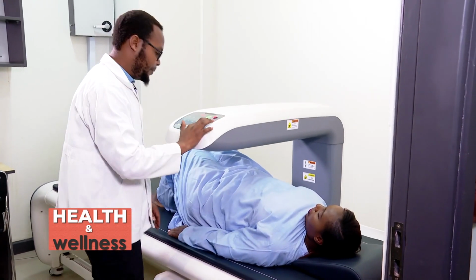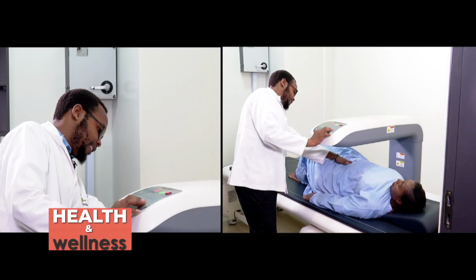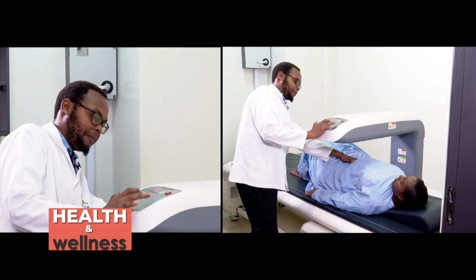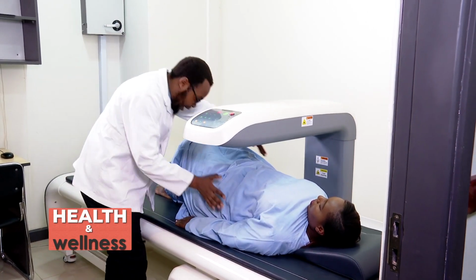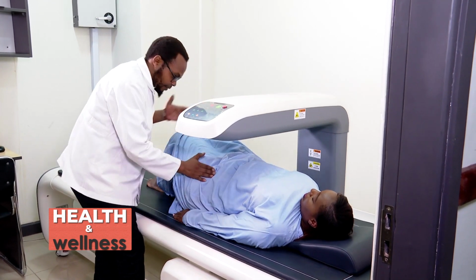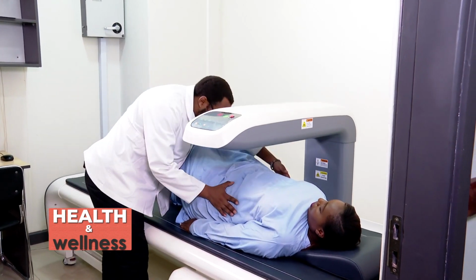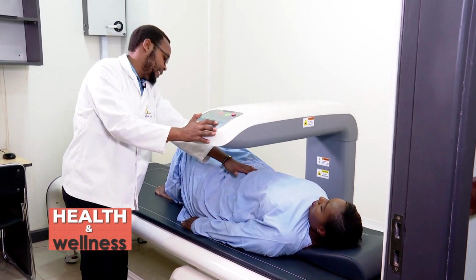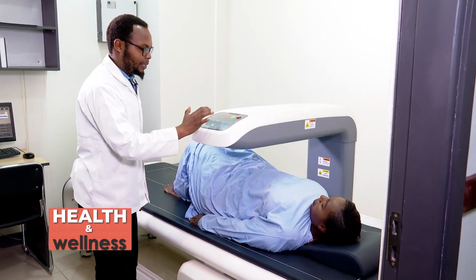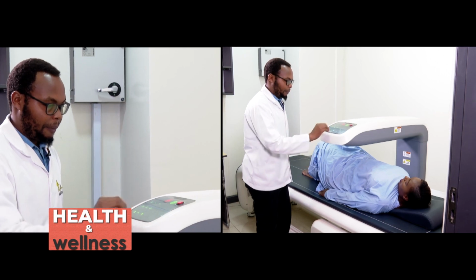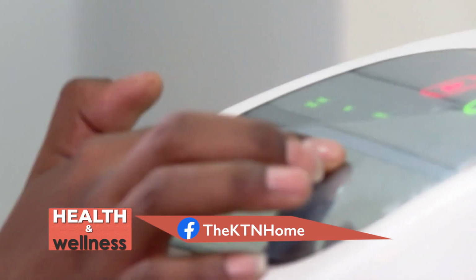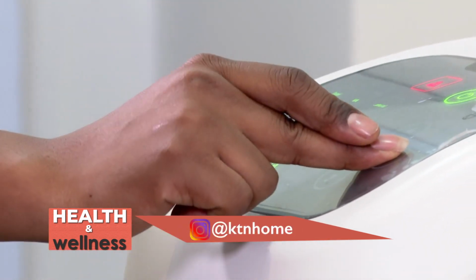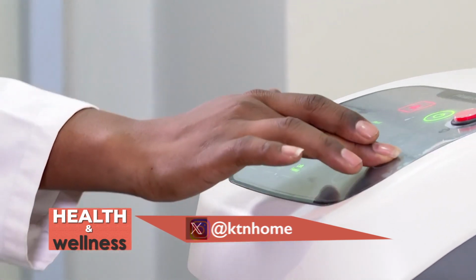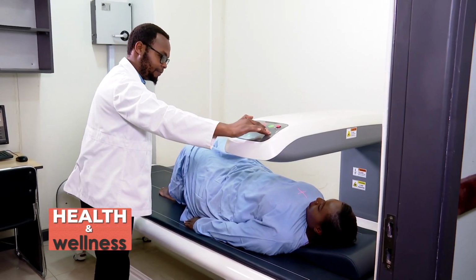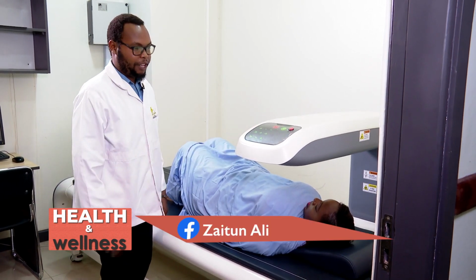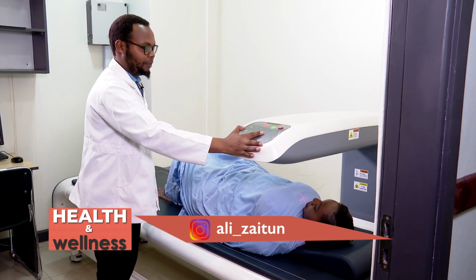So here we position the patient. The arm still moves. Patient will still remain in the same position. Make sure that the patient is well aligned at the center. We don't want to miss anything. We want to capture everything. Okay, once we are set like this, we start our scan. So here's how the scan goes by. The arm moves and the radiation starts. Here's how the X-ray detector moves. Once we are done, it goes back to its normal position.